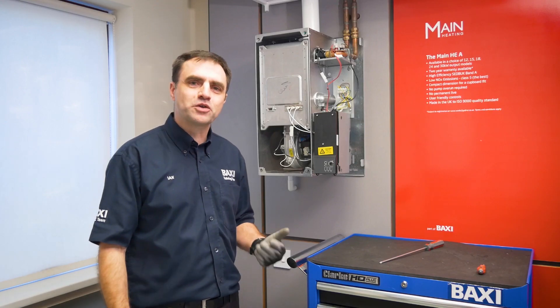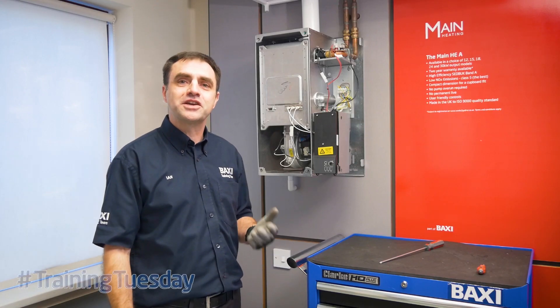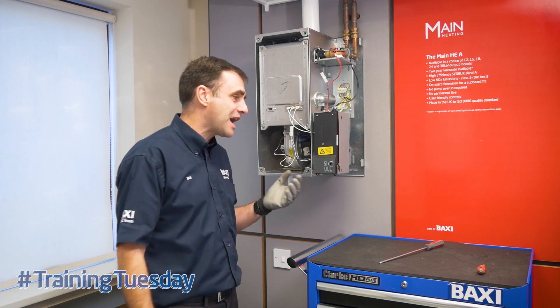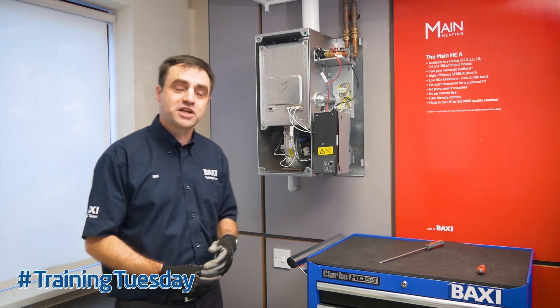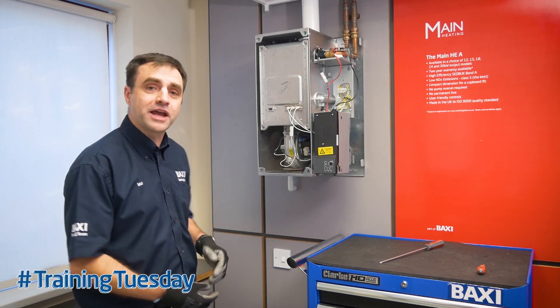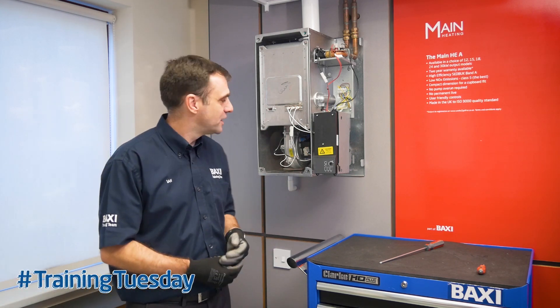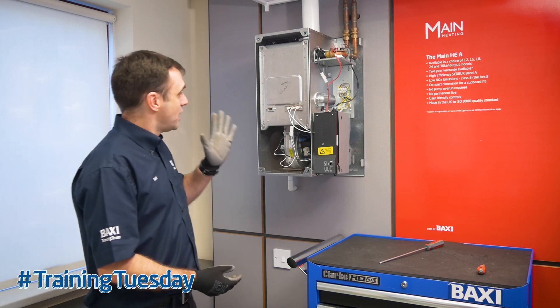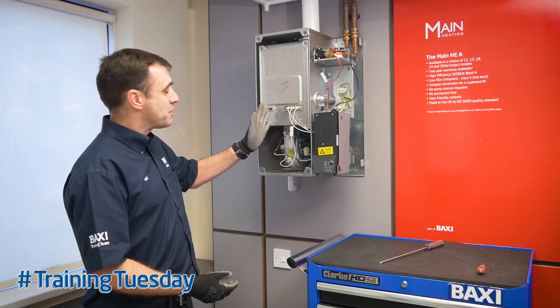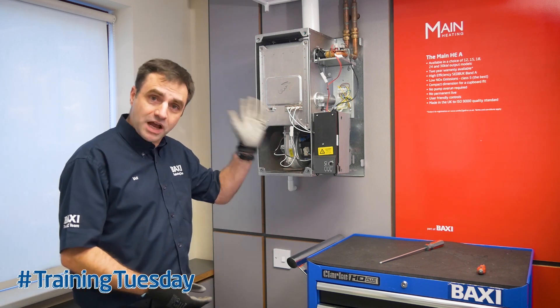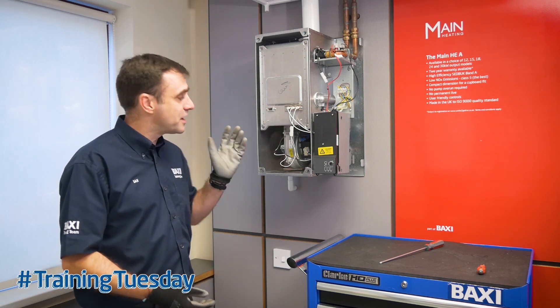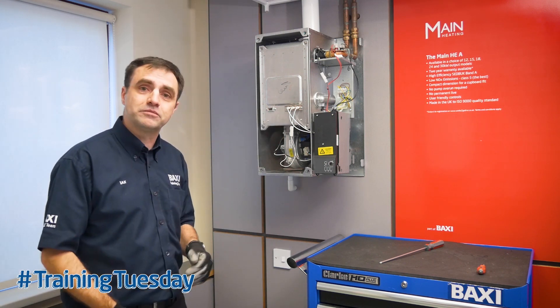Hi, my name is Ian and today we're going to talk you through some rectification issues that you may have on some products. We're using the main heat only boiler but it's not exclusive to this. The symptom is the flame comes on and goes off and comes on and goes off, and then eventually locks out.